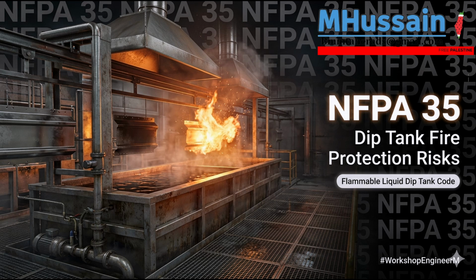Yep. And the math becomes exponentially harsher if you're processing unstable liquids. Oh boy, unstable liquids. Right. These are reactive chemicals that will vigorously polymerize, decompose, or become self-reactive under mechanical shock or temperature changes. So they're just looking for an excuse to react. Exactly. If you have an unstable liquid in a tank with venting under 2.5 psi, you multiply the base distance by 2.5. Okay. But if the venting is over 2.5 psi on an unstable liquid, you multiply the distance by 4. That is staggering. It really is.